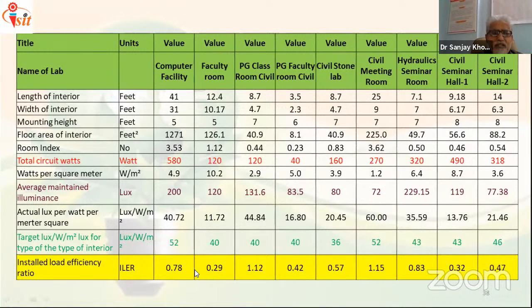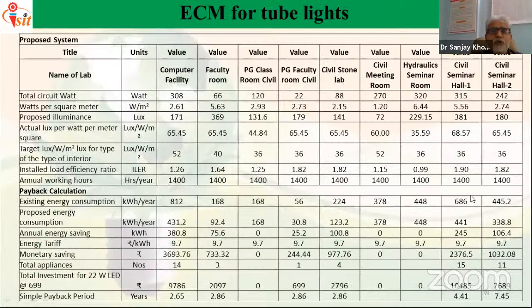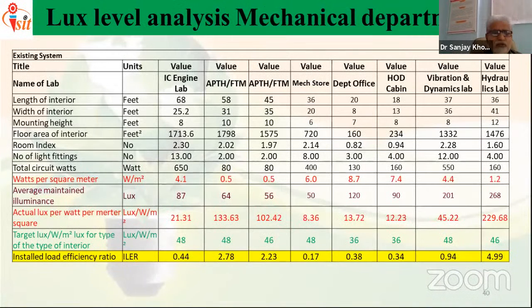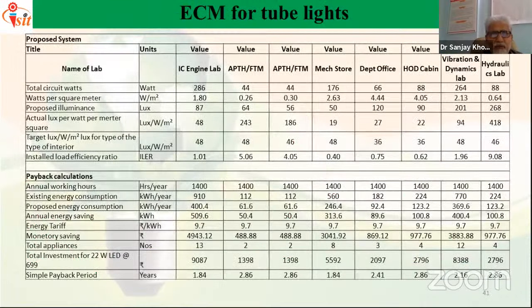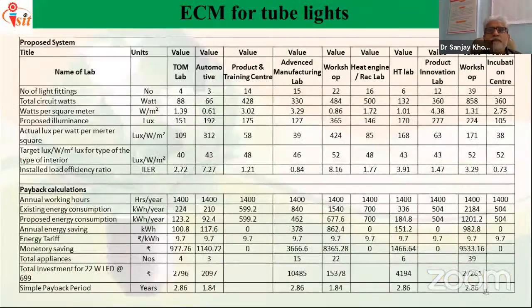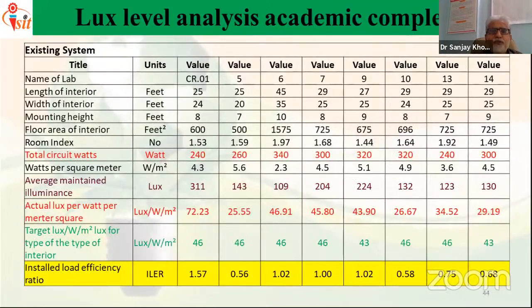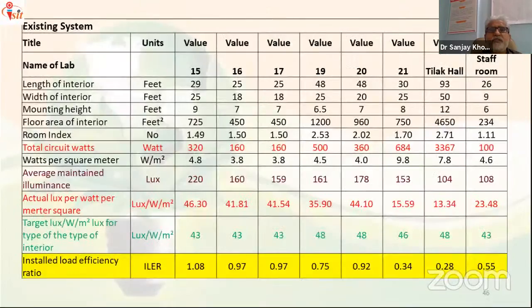Now similarly, 78 means it's better, 29 means it's less, so we recommended them to go for additional tube lights there. Generally the payback should be below 3 years and ILER should be above 0.75. If it's below 0.75, we ask them to add tube lights; if it's above 1, we ask them to reduce tube lights. So for every lab, we do this analysis and accordingly submit our recommendations to them.